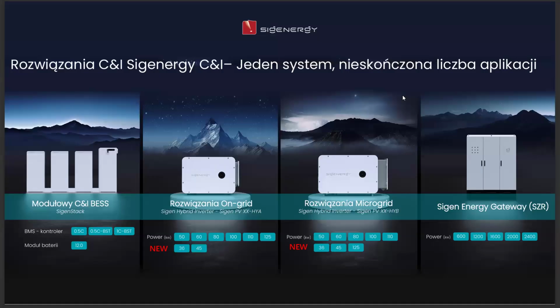3. Q3/Q4 Roadmap, Liquid Cooling and Megawatt Scale Solutions. Is Sigenergy stopping at passive cooling? Absolutely not. In Q3 and Q4 this year, we are launching liquid-cooled solutions. 261 kilowatt-hour cabinet, dedicated to hybrid applications, configurable in systems from 1 to 4 units. Utility/farm scale systems, including a 350 kilowatts hybrid inverter and dedicated 361 kilowatt-hour cabinets. With this advanced cooling technology, we will be able to achieve system response times of around 0.125 seconds. That is top-tier global performance for grid stabilization and industrial applications.